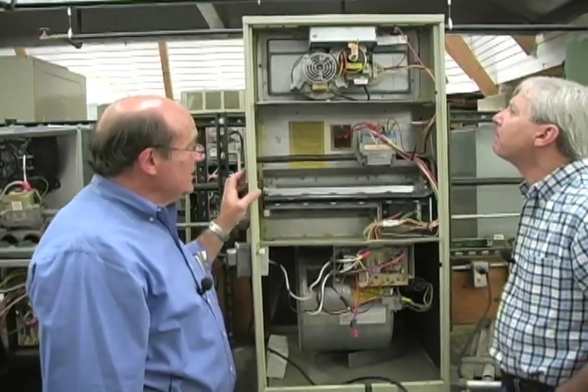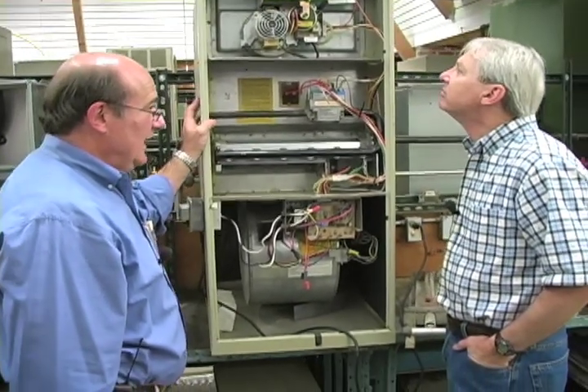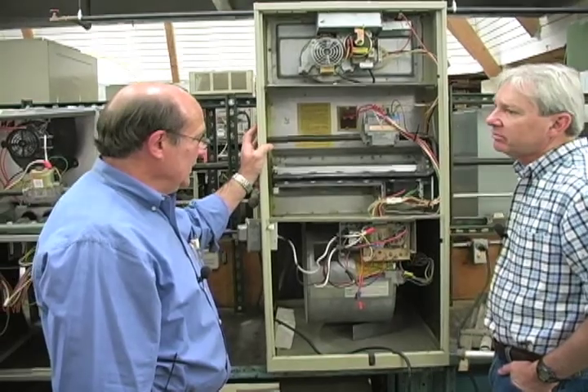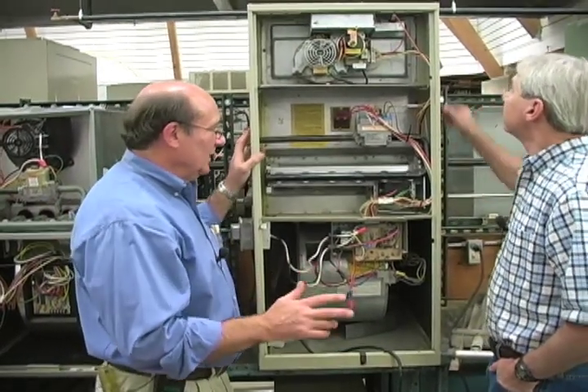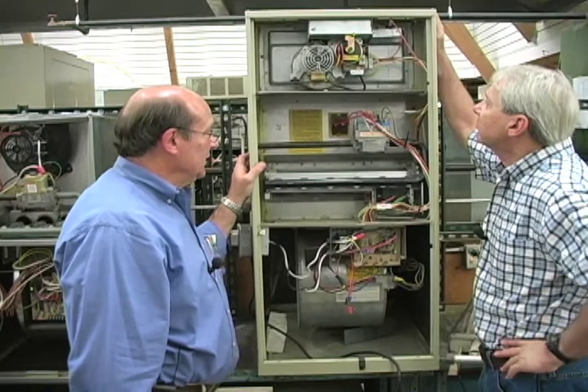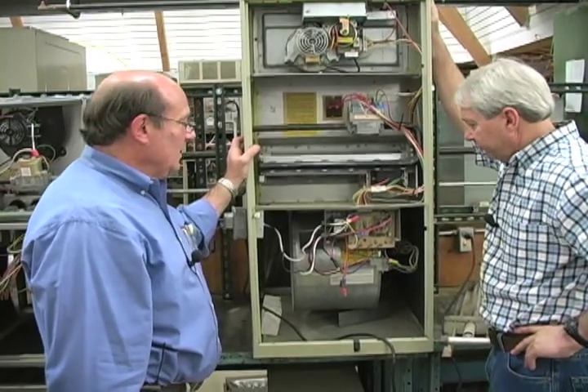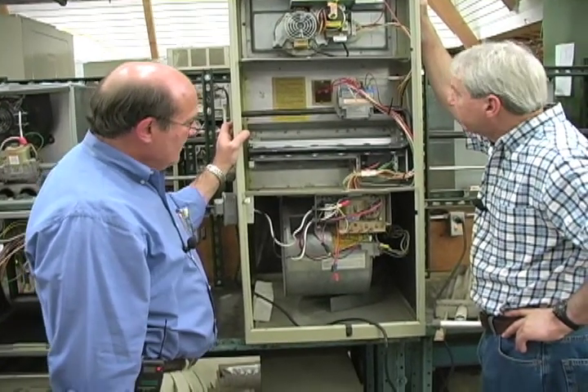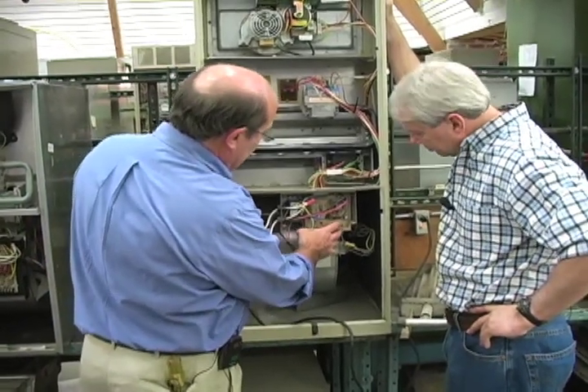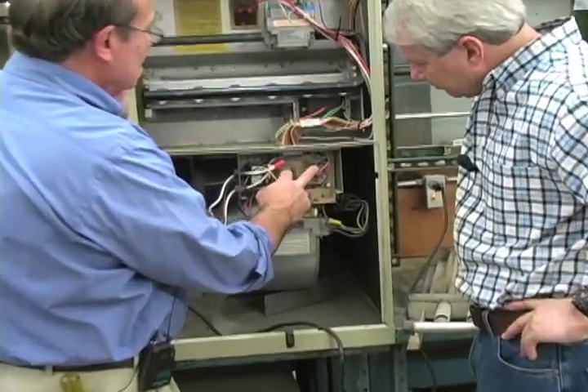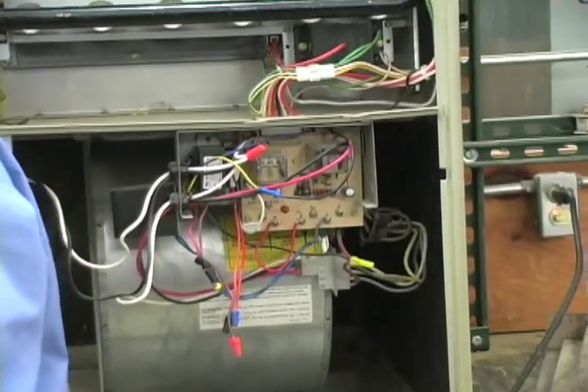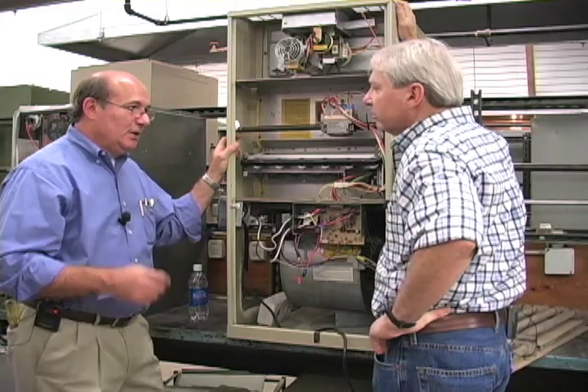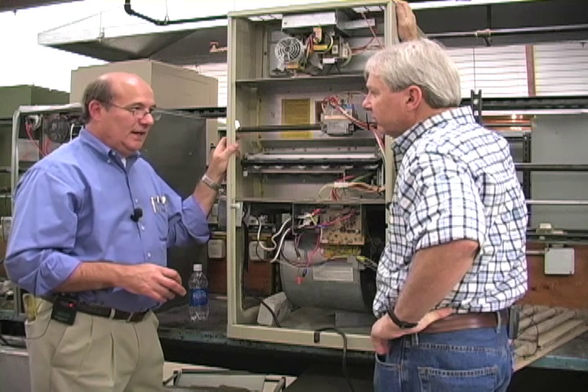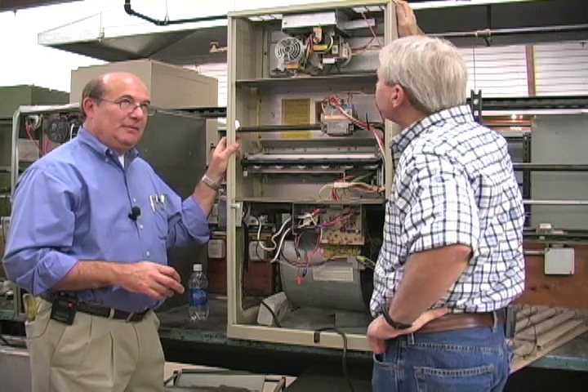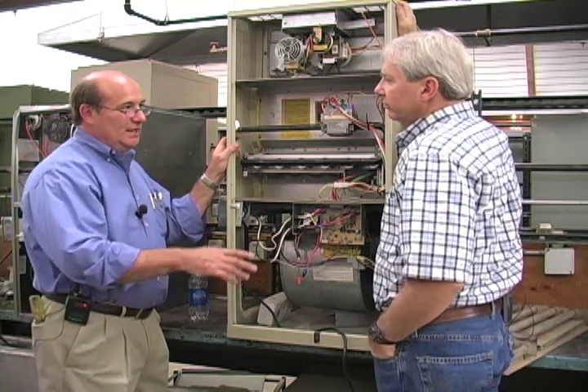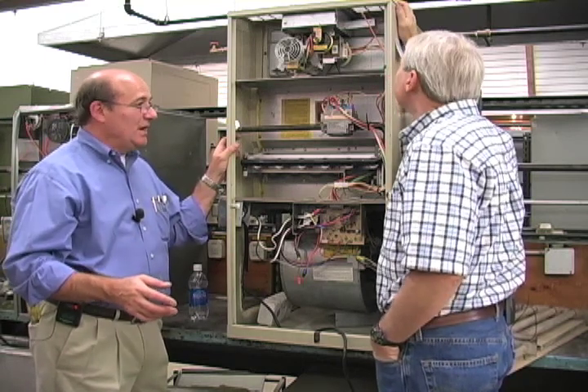All right, so Ken, this is a next generation furnace. This is 80 to 85% efficient. All the manufacturers test a little bit differently on it, but they're in that 80% efficiency range. This is quite a bit different from our other furnace. It's got a whole lot more stuff on it. It's got solid state circuitry on it. Still has some manual relays and stuff, but primarily it's got 2 distinct functions that give it its much higher annual fuel efficiency rating. An annual fuel efficiency rating means that over the whole 1 year of operation of this furnace, it's going to give you better efficiency.